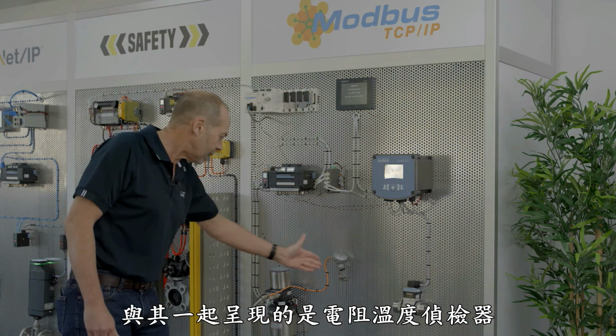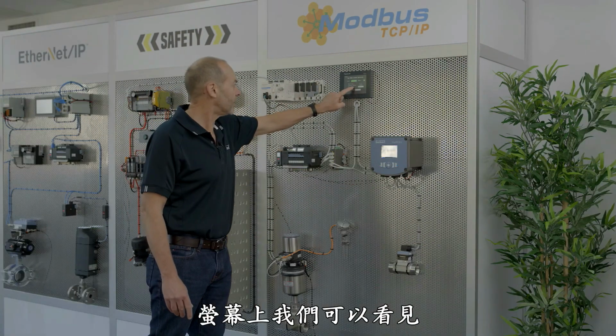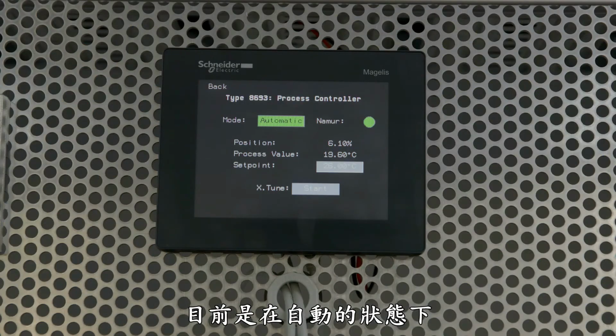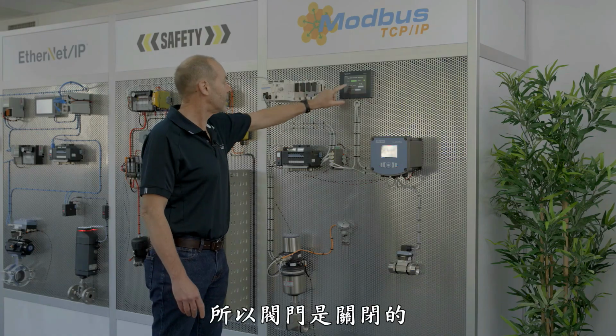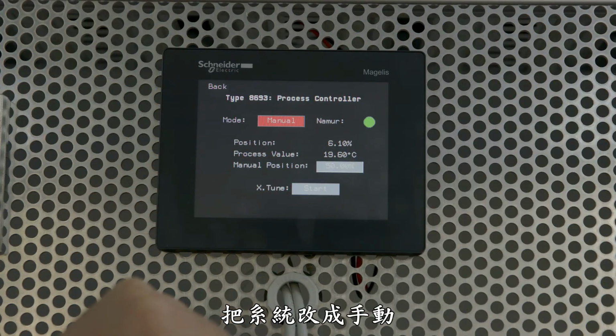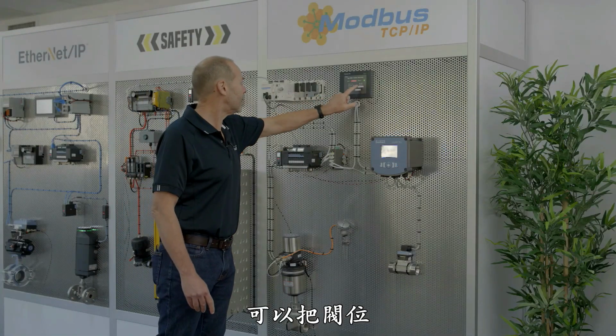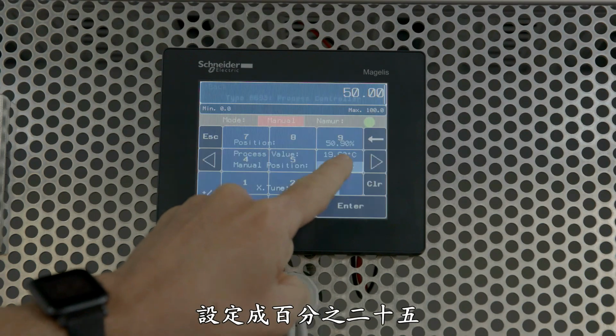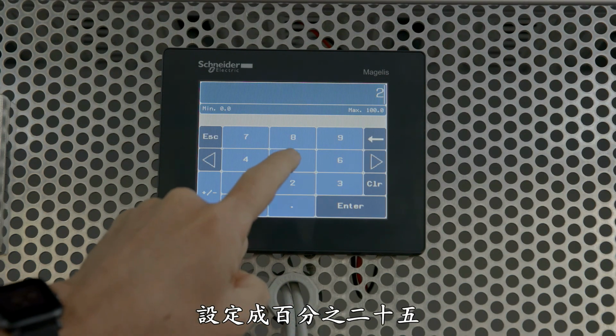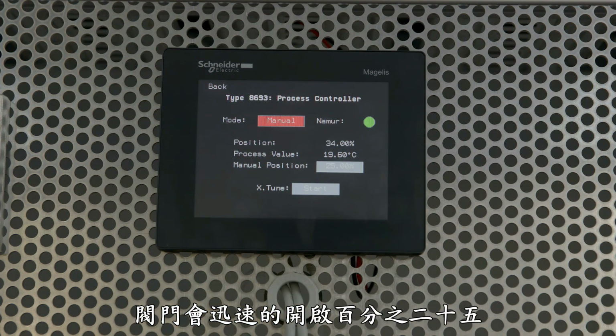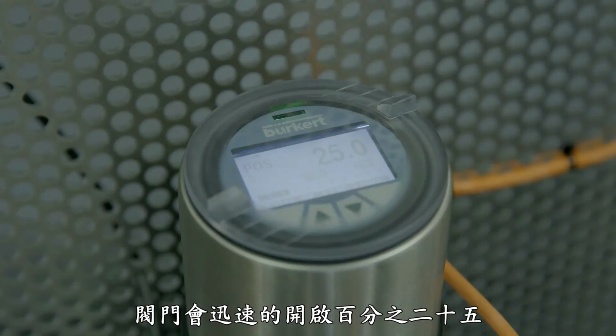So we're showcasing it here with an RTD. If we have a look at that on the screen, we can see that it's in automatic and it's at 26 degrees set point and the process value is low, so the valve is shut. We change that over to manual and we can actually send a valve position directly to the valve. Let's set it to 25%, enter, and the valve goes immediately to 25%.